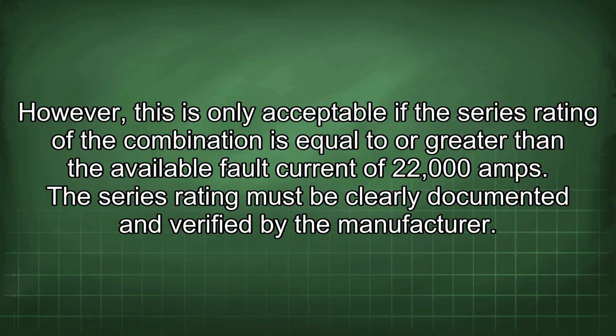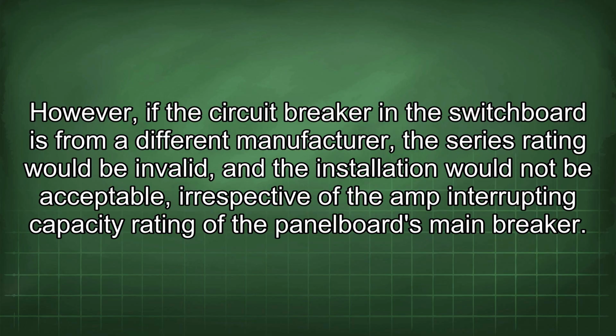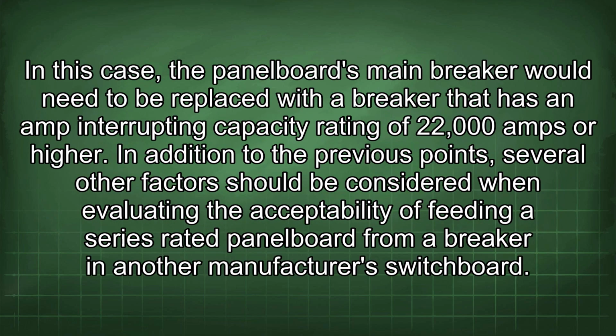The series rating must be clearly documented and verified by the manufacturer. However, if the circuit breaker in the switchboard is from a different manufacturer, the series rating would be invalid and the installation would not be acceptable, irrespective of the amp interrupting capacity rating of the panel board's main breaker. In this case, the panelboard's main breaker would need to be replaced with a breaker that has an amp interrupting capacity rating of 22,000 amps or higher.